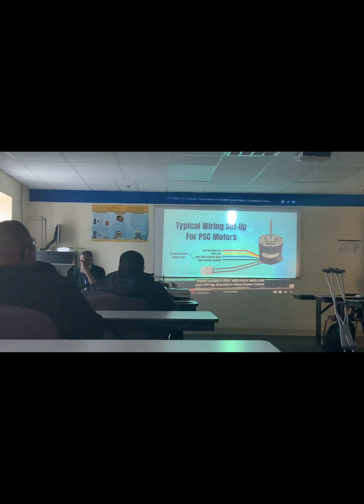They're pretty simple to switch out. Are you aware that the colors of those split-phase motors represent these speeds? And they're always representing those speeds. Sometimes you use low speed on the furnace, but you might need medium low, or you might need medium high because you need more airflow because of duct design. Will you read this and tell us the colors for it? Okay. Red is traditionally low speed for heat. Black is traditionally, as they say here, for cooling, because cooling air is heavier, you need more force to push it, more CFMs. So that's the traditional hookup, and you don't use all four of them at one time. You only use two, one for heating, one for cooling. That makes sense?